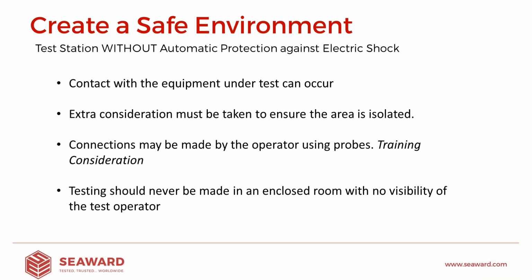The other thing to think about is, in many instances, the operator may have to use physical test probes in order to make the test connections. So that may not be possible to do inside an enclosure anyway. And if that is the case and we are using probes, we need to consider training the operator to be able to use those probes effectively and ultimately safely. Back to where we spoke about, in this kind of environment, the operator can come in contact with the product, never ever have them testing in an enclosed room where there's no visibility.